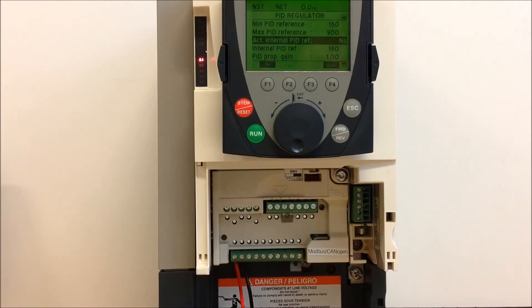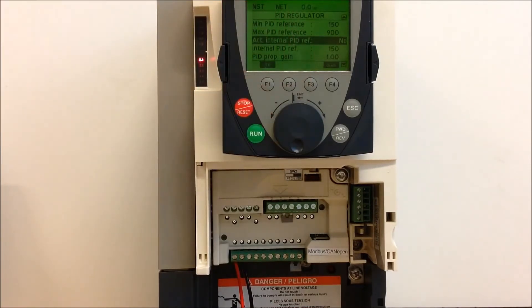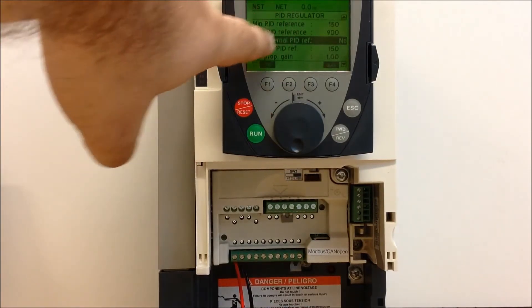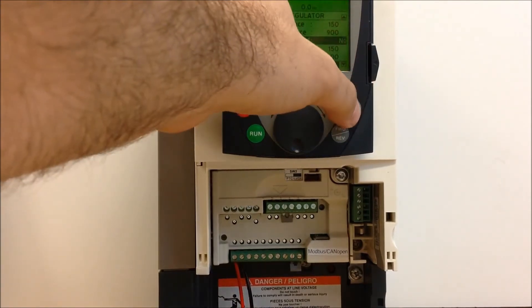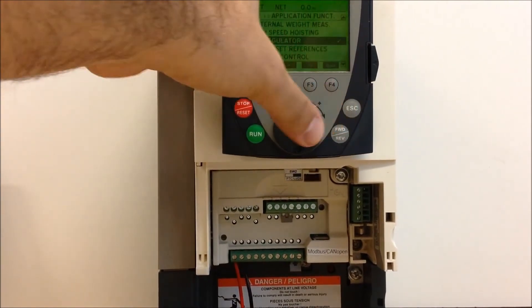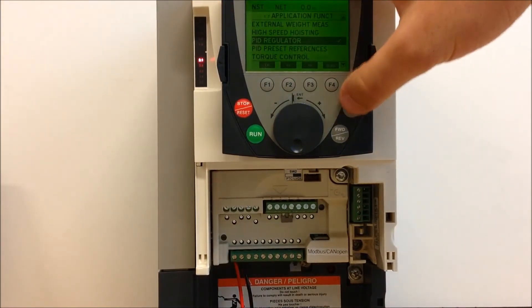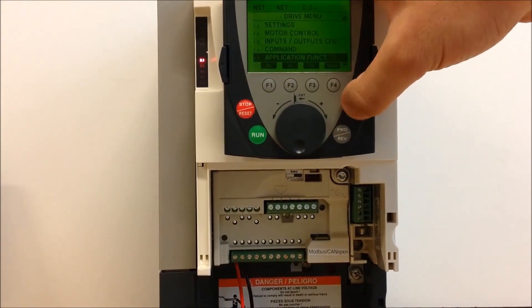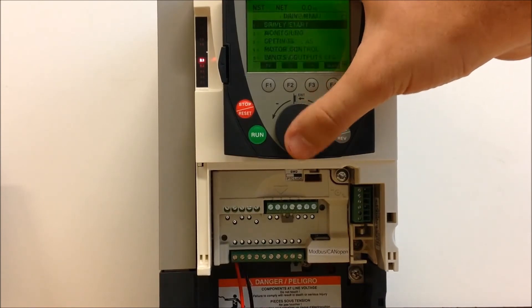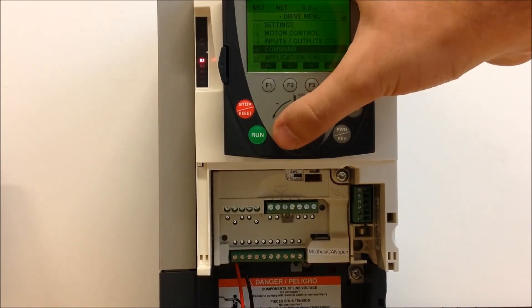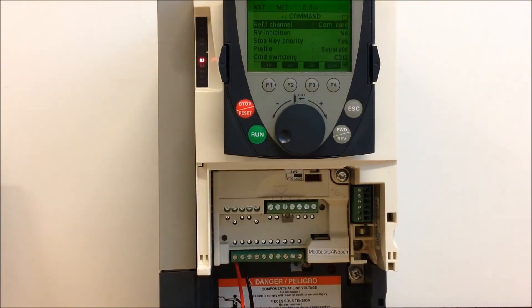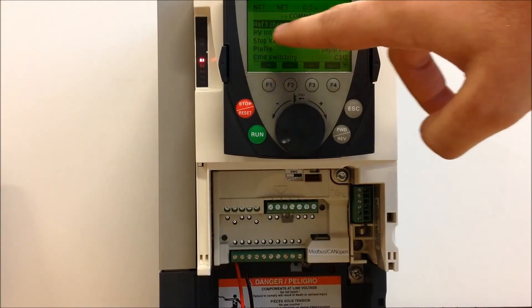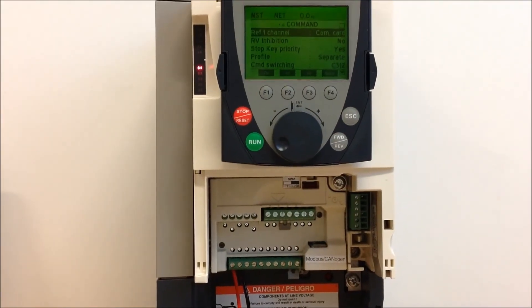But let's just say you want to use a keypad dial. So with the PID programmed, you want to keep it set to no. And now, with that set to no while the PID feedback is active, you can now go into your 1.6 menu under drive menu, and with that ACT internal parameter set to no, the drive will look at your reference one as a means of a setpoint now.